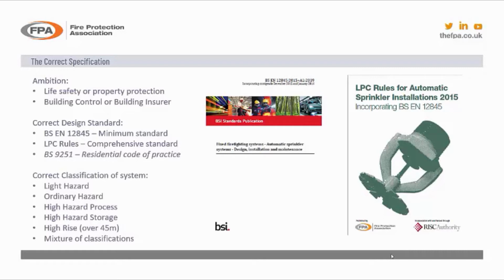As can be seen on the right-hand side there, we've got the 2 different standards that the UK rule. So the correct design standard might be to an American standard where you've got NFPA, or if it's an insured business or building with FM Global, they will have their own FM data sheets. But most likely in the UK, if a sprinkler system is required for life safety or property protection, it falls into 2 categories. We have on the left hand side there, as shown on the screen, the BS EN 12845, which is a minimum standard. It is there for enhancing people's chances to escape from the building before collapse.